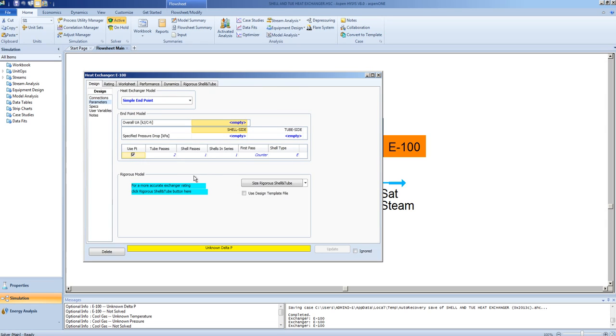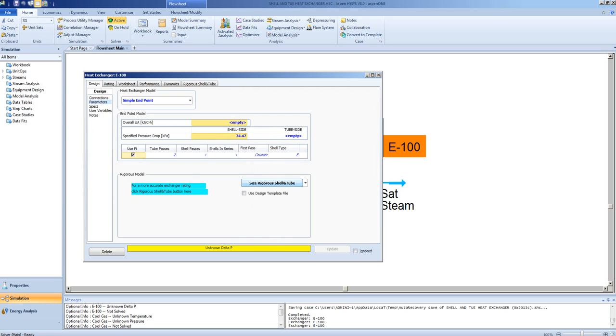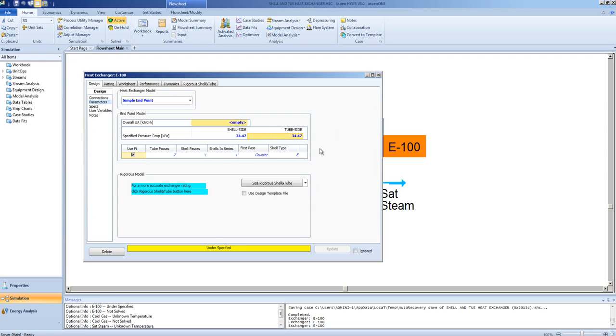One parameter that must be specified is the delta P. With respect to shell and tube heat exchangers, a typical delta P would be around 5 psi. This, of course, varies with the exchanger design, the number of tubes, the tube diameter, the velocity through the tubes, etc. The degree of fouling.